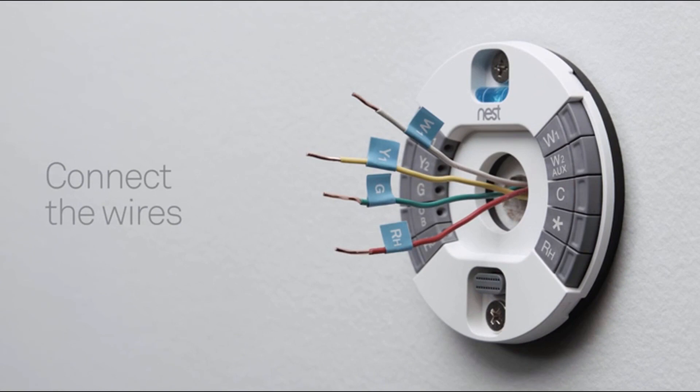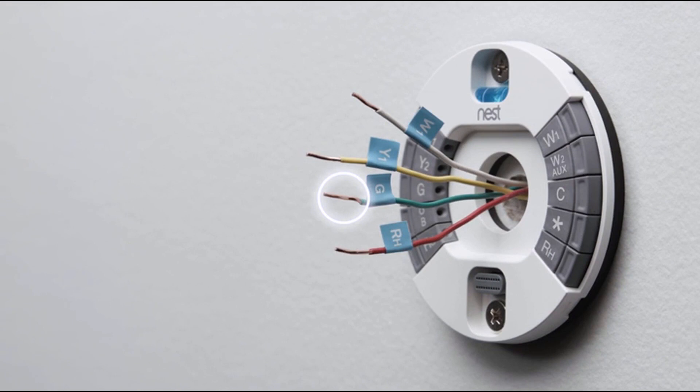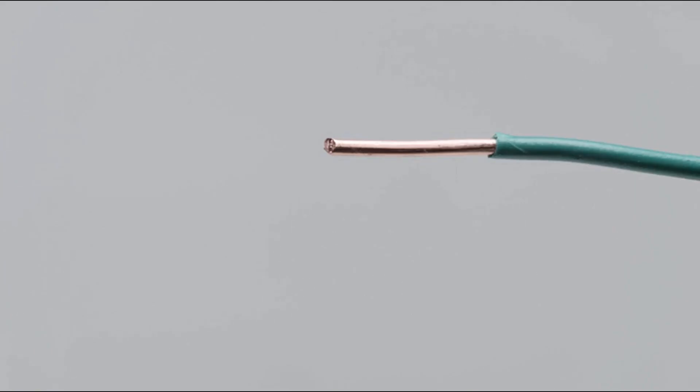Now it's time to connect the wires. Check the ends of your thermostat wires. They should be straight. If not, re-strip them and trim the ends, leaving 3 eighths of an inch or 10 millimeters of wire exposed.